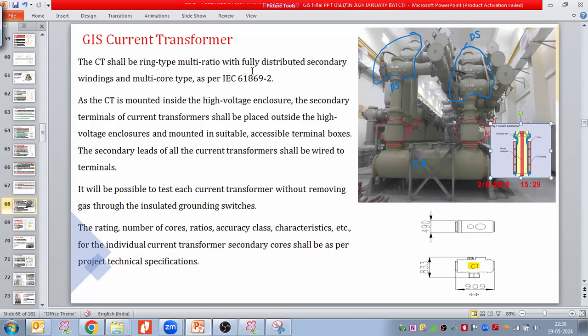So the CT cell is ring type, multi-ratio, multi-core, same as we have discussed in the AIS, with fully distributed secondary winding and multi-core type as per IEC 61869 part 2. The CT is mounted inside the high voltage enclosure. The secondary terminals of the CT shall be placed outside the high voltage enclosure. Could you see this portion in the drawing, my cursor here? This is our secondary terminal.